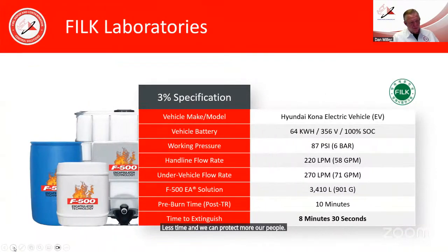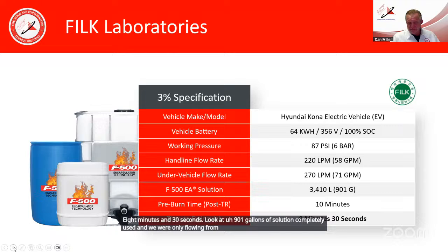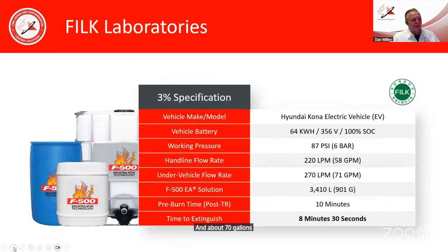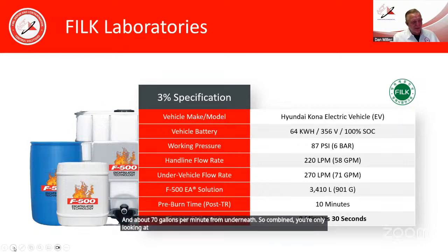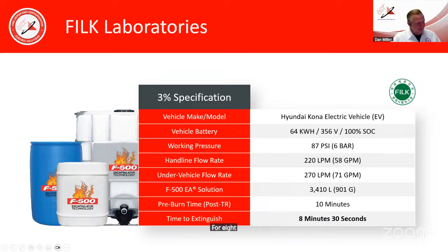The big thing there is the time figure at the bottom: 8 minutes and 30 seconds. Look at 901 gallons of solution completely used. We were only flowing from that hand line less than 60 gallons per minute, and about 70 gallons per minute from underneath. So combined, you're only looking at about 120 to 130 gallons per minute overall for 8 minutes. Not too bad.